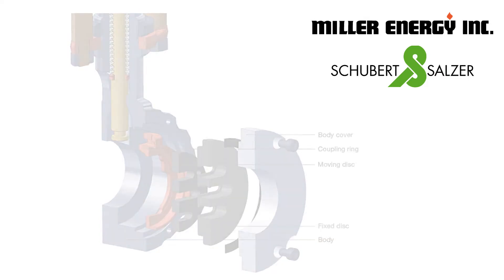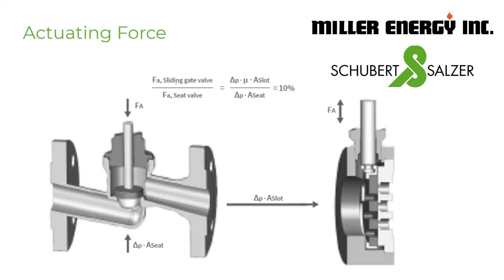The outstanding feature of the sliding gate valve is the actuating force, which is approximately 10% of that required to actuate a globe valve of the same nominal size and the same differential pressure. This permits the use of much smaller actuators, even though both designs of the same nominal size have about the same flow rate. This beneficial feature stems from the fact that closure is transverse to the flow direction in the sliding gate valve, not against it as with the globe valve.